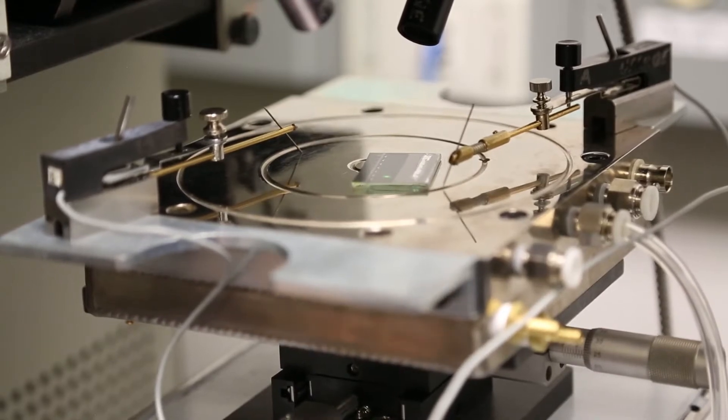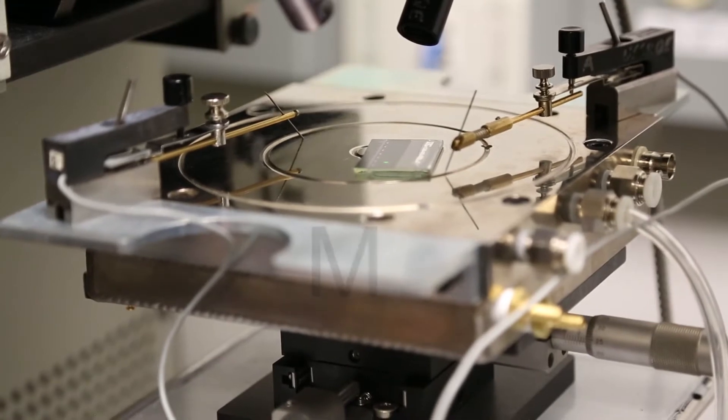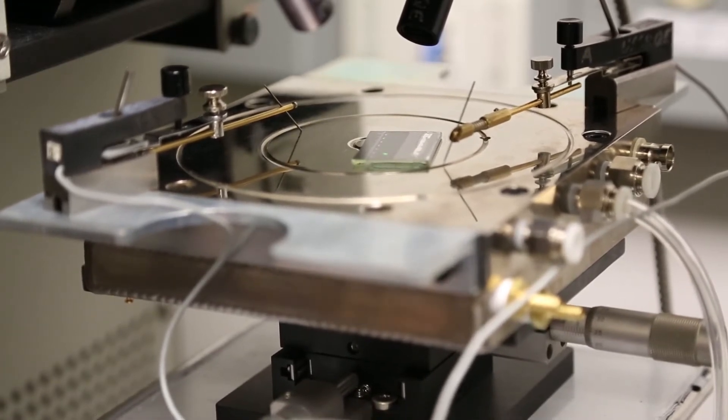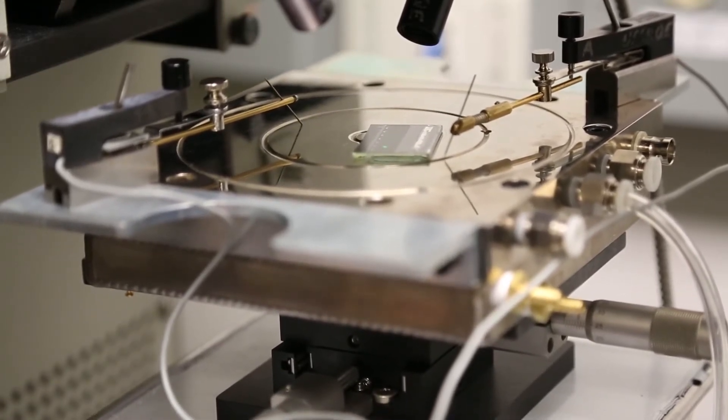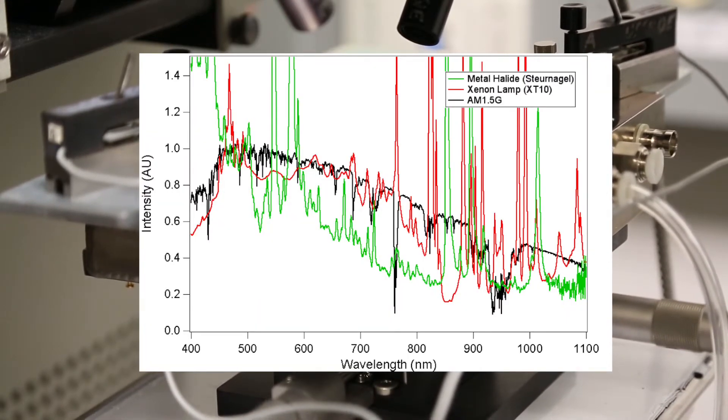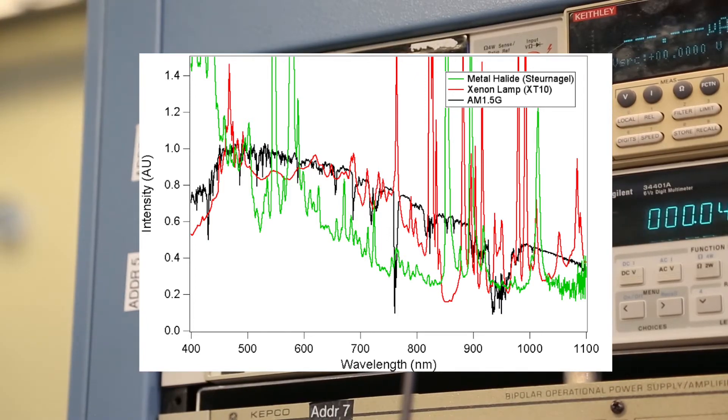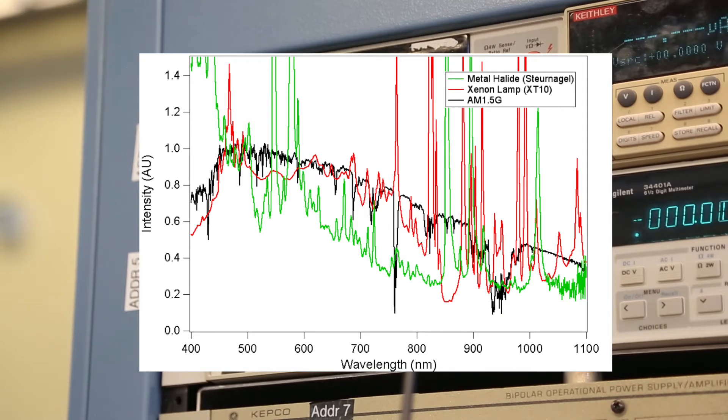Corrections can be made using the spectral mismatch factor M. This captures the difference in intensity between the AM 1.5G solar spectrum and the lamp spectrum used for solar simulation. In the graph shown, the wavelength versus intensity of two common solar simulator lamps is compared to the AM 1.5G spectrum. It is clear that there is spectral mismatch shown by varying light intensities at given wavelengths when compared to AM 1.5G.